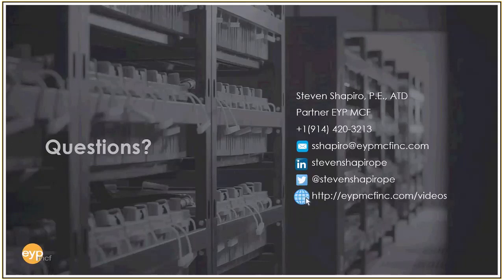People are now putting a lot of this infrastructure outside, so transformers, distribution gear, and systems are going outside, so not having to cool this kind of equipment becomes less of an issue. Some of these systems are actually going into shipping containers, and then obviously you need dedicated cooling for the UPS and batteries in that environment. But we're finding that the cooling technology overall for the data center is what's driving PUE, not the electrical infrastructure associated with it.